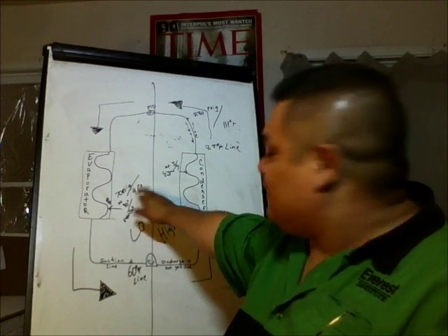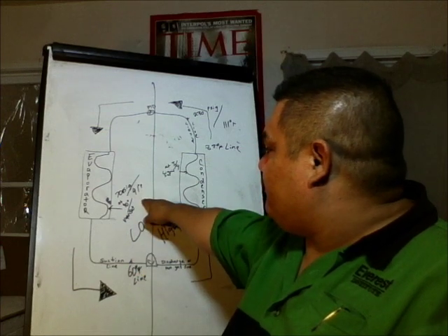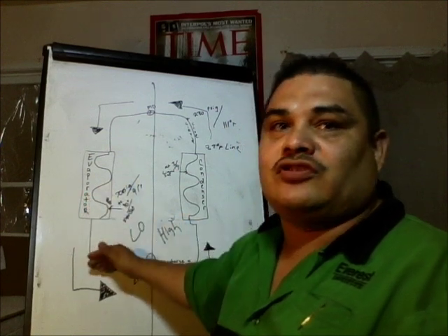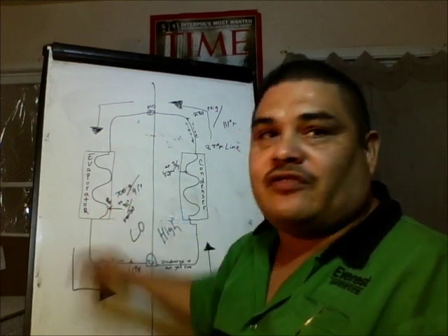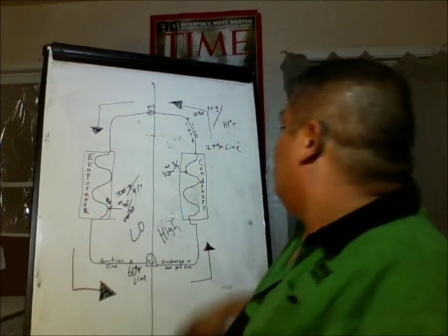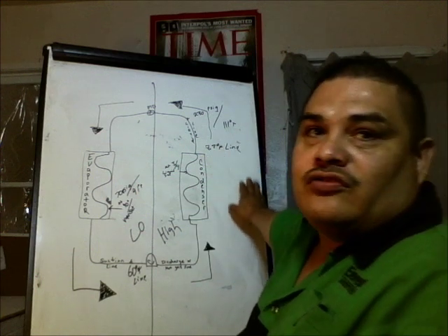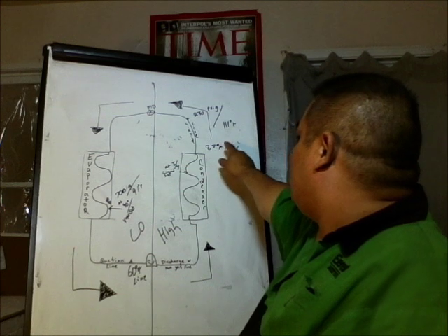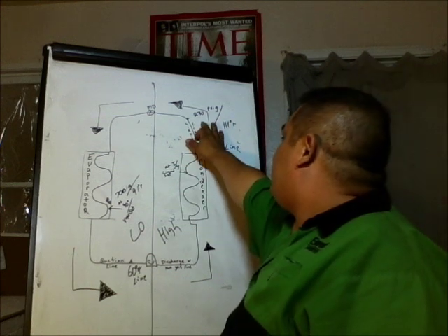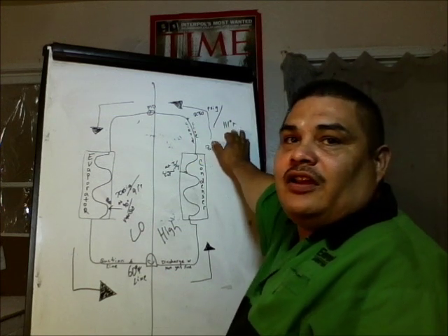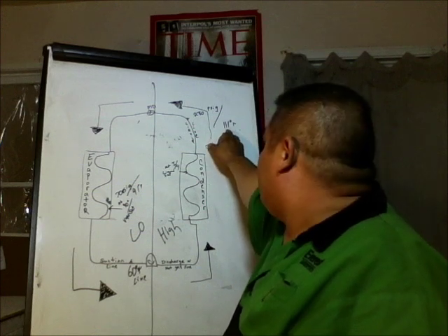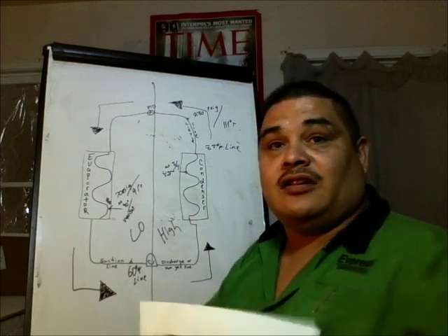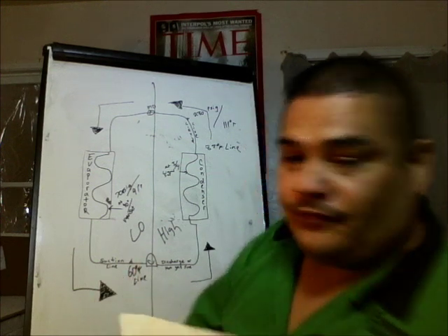That's your suction saturation temperature. That's the temperature of it coming out. Once you hit 90%, that's the temperature of it coming out of the evaporator. And then going into the condenser, you're looking at after saturation. It was 230 PSIG, which corresponds to about 111, give or take, saturation temperature inside the line. That's the temperature of the coolant inside.